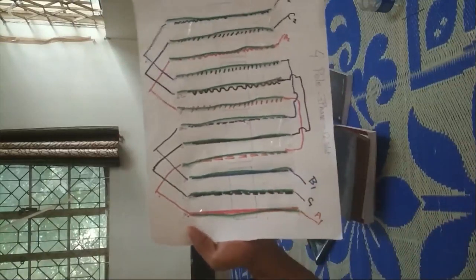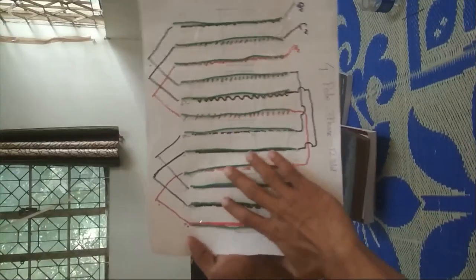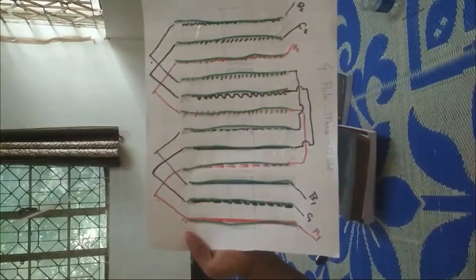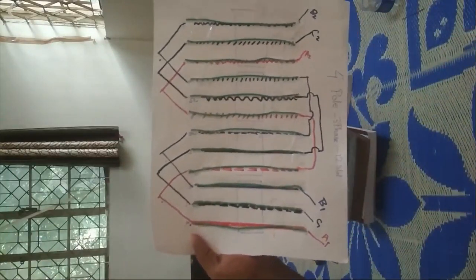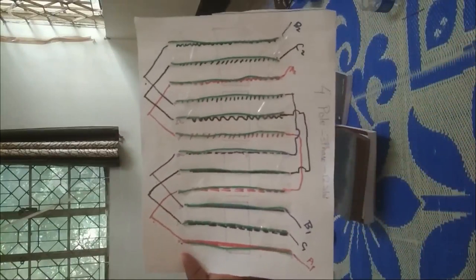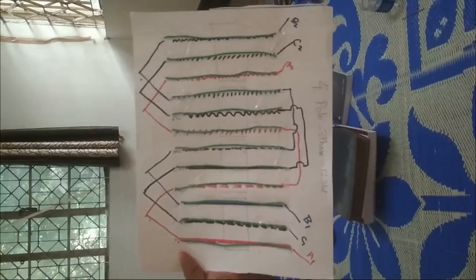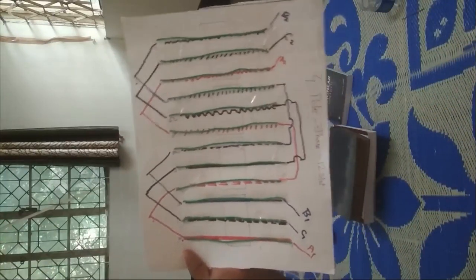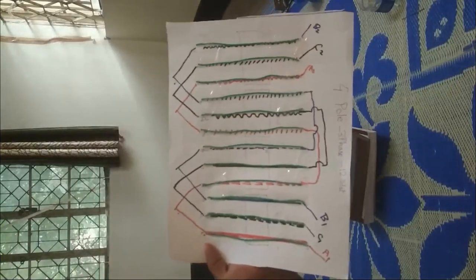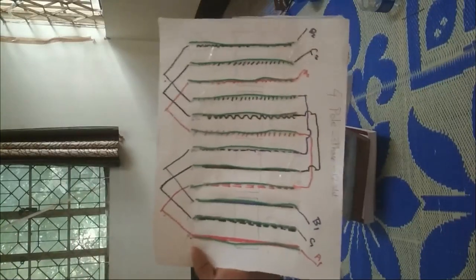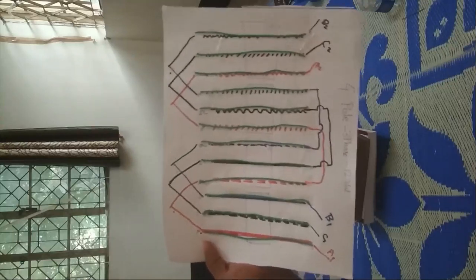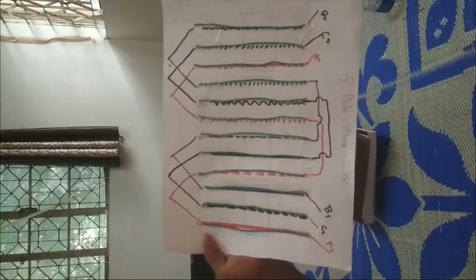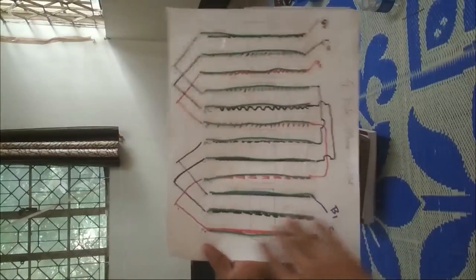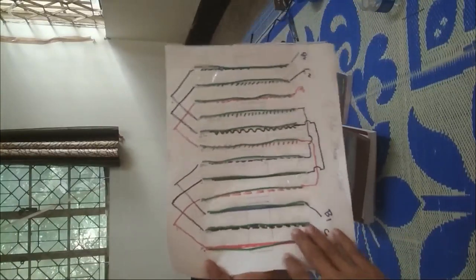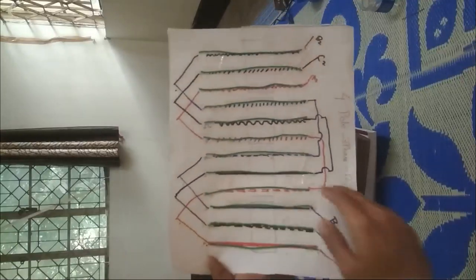First, let us complete the A phase connection. How many A phase conductors will there be? You have to understand slot per pole per phase. Here how many slots do we have? 12. How many poles? 4. How many phases? 3. So slot per pole per phase is 1. That means one A phase red conductor will belong to north, then another will belong to south.